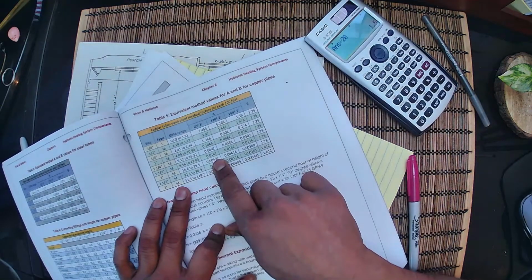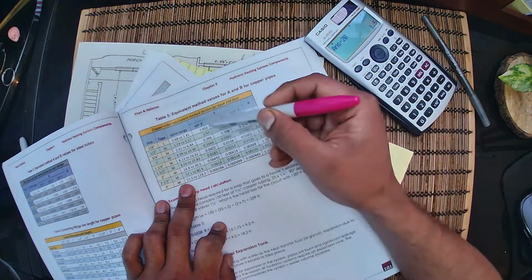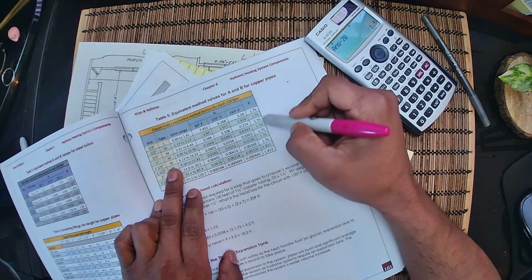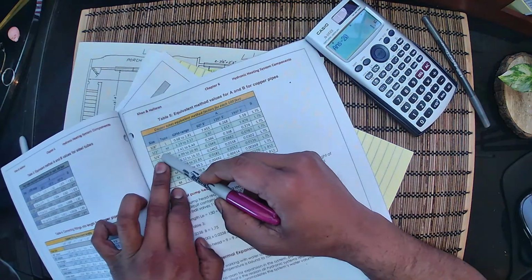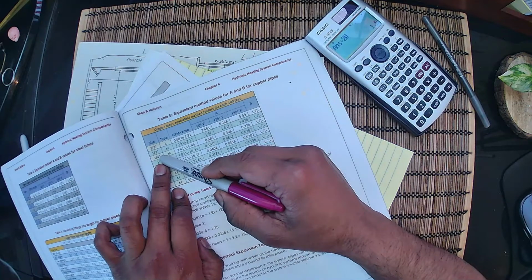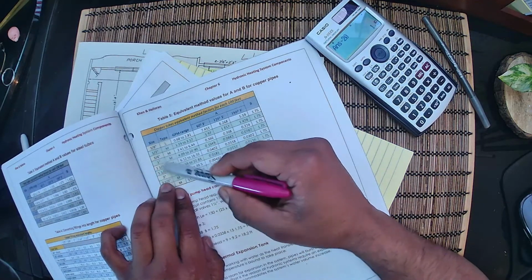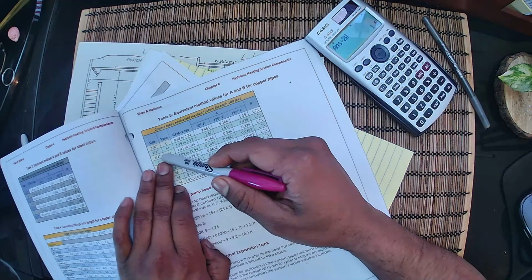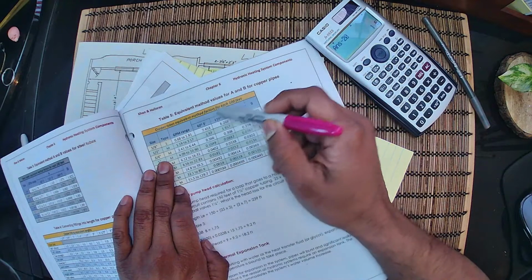So here is the table. It's page 101 in my book. And B is going to be 1.75. And if you look here, it's based on the size of the tube. So we're using 3/4, or you can use whatever you want, it could be anything up to 2 inches, but the most common is 3/4. And we can go and verify that. You saw that in the last lecture.